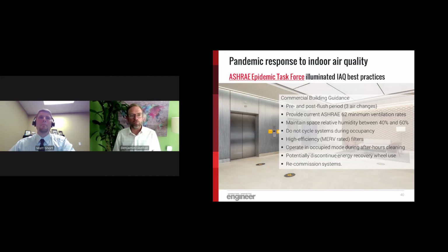Yeah, Matt, as we go into what commercial buildings have done or are currently starting to do, the ASHRAE Epidemic Task Force responded very quickly with, as you alluded to, a lot of best practices, things that we should be doing in buildings if we're not already. But looking at the commercial building guidance, for example, and there are others, there's guidance for schools and all kinds of different types of buildings. So check out that resource.